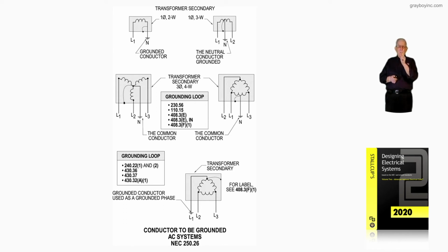You really start with 110.15. And that says it's got to be orange in color, or it's got to be identified in an identification manner that's acceptable to the authority having jurisdiction or the utility. And some utilities used to let that high leg be red, and that's why they called it the red leg. Some people called it a Y leg. Others, high leg. Usually those three names, one of them catches it, but by code it's a high leg.